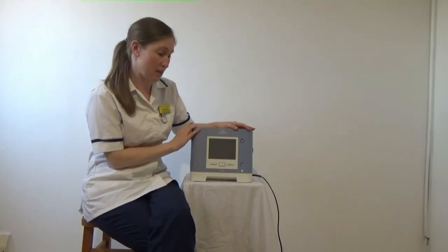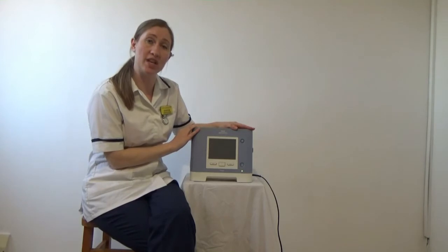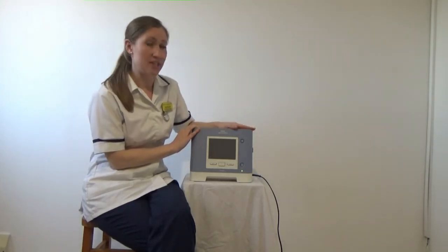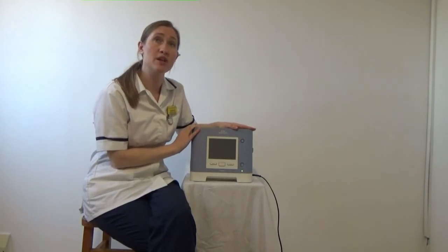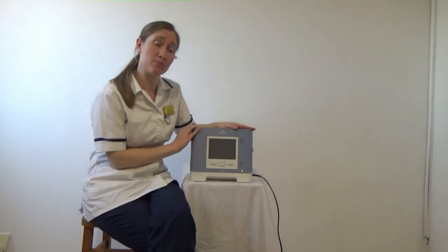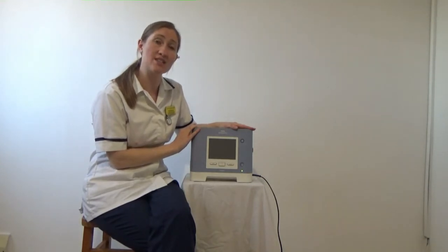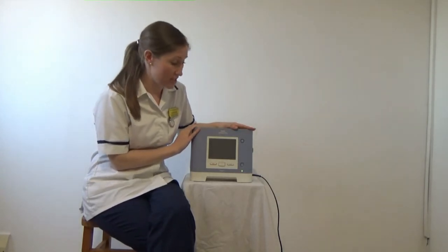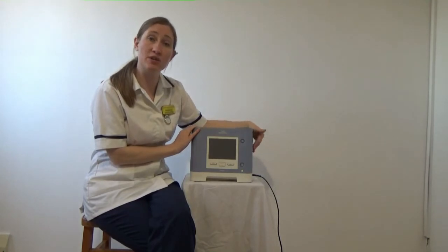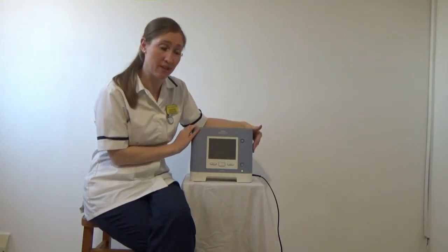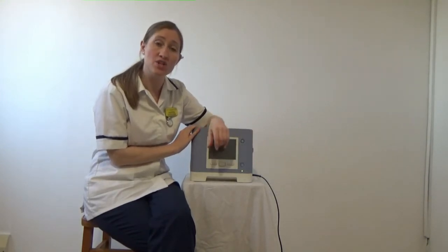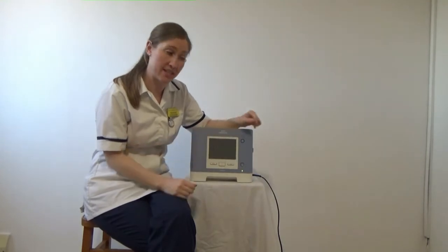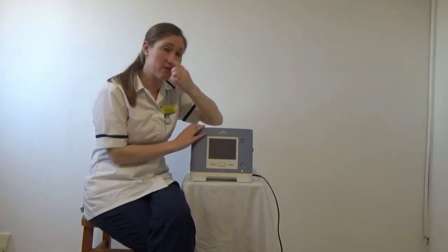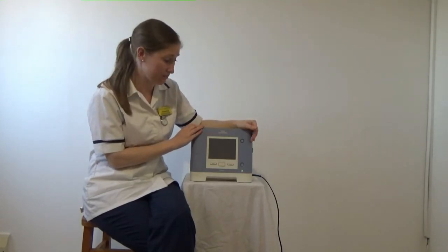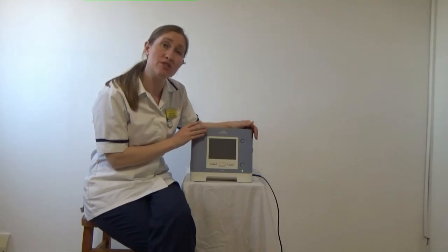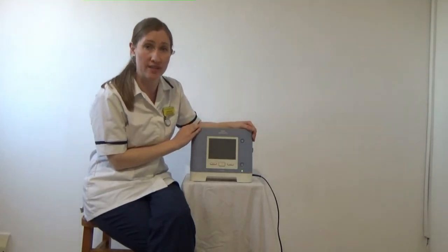Most of the medium priority alarms suggest that there is either a leak or a blockage in the circuit. Alarms that suggest there is a blockage or occlusion in the circuit include low circuit leak, high expiratory pressure, low expiratory pressure, and high inspiratory pressure. These all suggest that there is a blockage, in which case please check if you're using a filter that it has been changed recently. If you are using a grey hose, check that this has not become kinked or occluded at any point. Please also check the expiratory port on the mask to check that this is not blocked. If the issue is not resolved by any of these, you may wish to contact your NIV department for further advice.